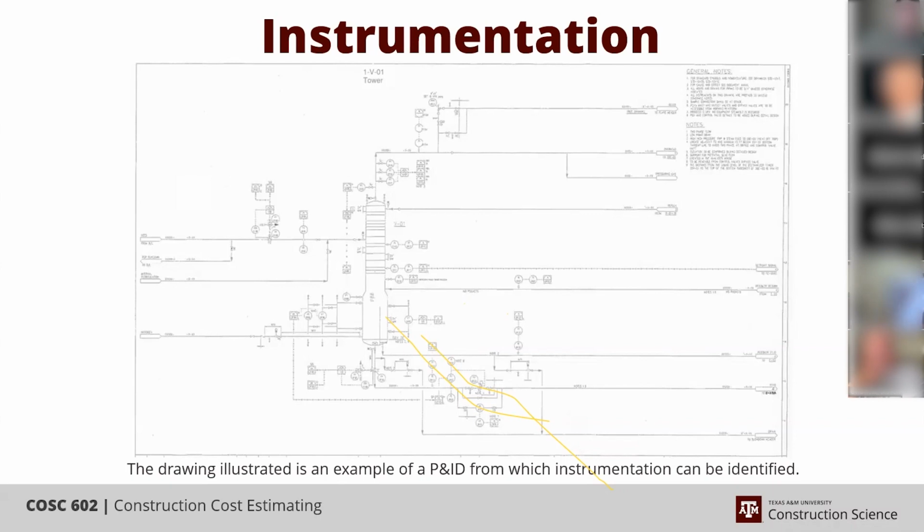So we can collect a whole number of wires with digital signals on them in this area here, run it to a charm, and then you might go in with 50 and you come out with 5 optical cables, and that runs to the control room, and the control room then reinterprets it and sends the signal wherever it needs to go. And the concept is that now, instead of having 50 wires running around there, you have 5 cables.